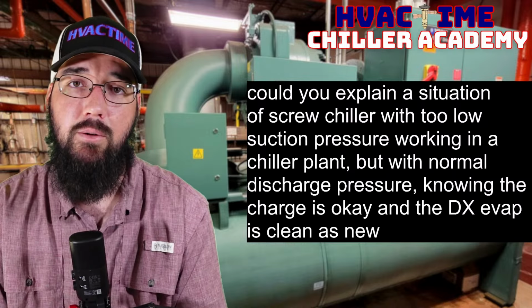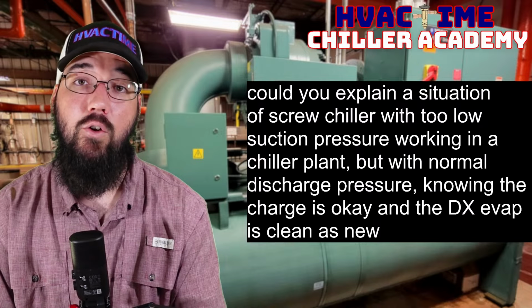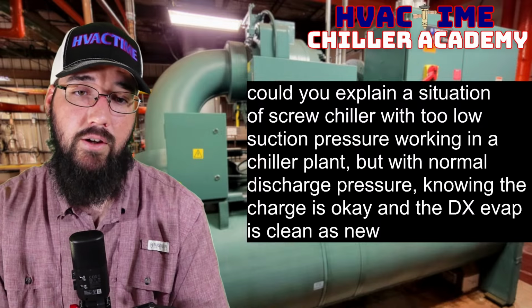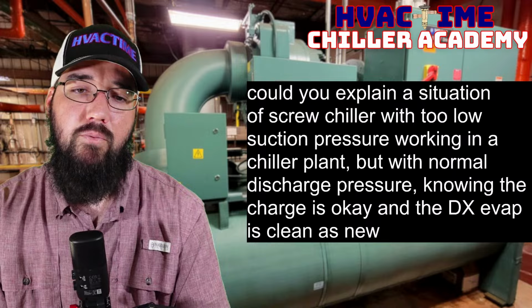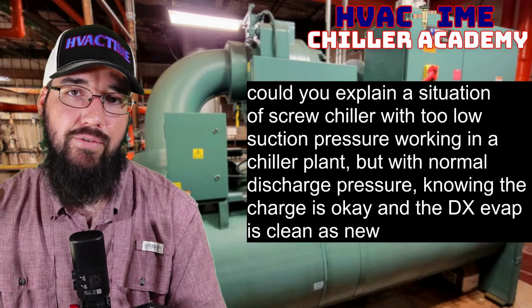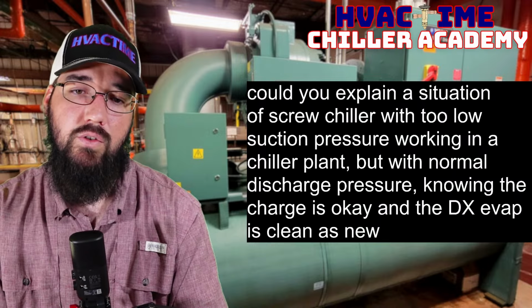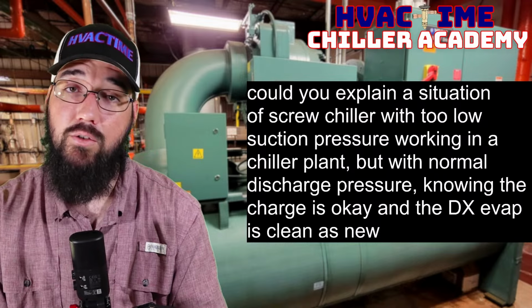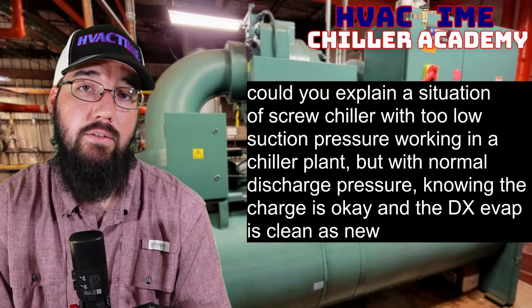That machine should be able to really stretch its legs and open up, and you're going to see those higher approach values. So I think first we need to make sure we're defining what is too low of a suction pressure in the first place. That also comes back to, what is your leaving water temperature?